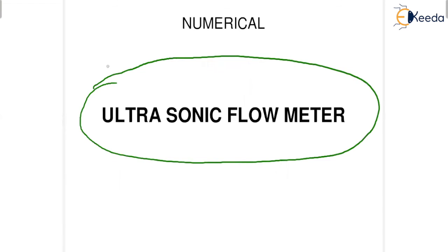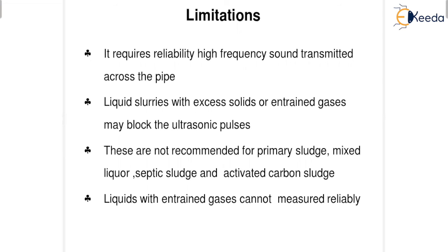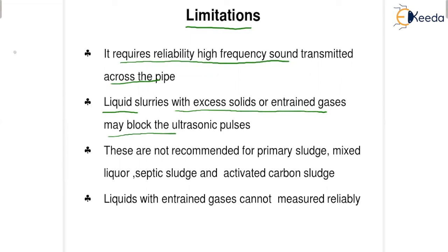Before that, I'm going to conclude with the limitations. It needs reliable high frequency sound transmitted across the pipe; it gives only stable frequency sound across the pipe. Liquid slurries with excess solids or entrained gases may block the ultrasonic signal. So the limitation is that the liquid passing inside the pipe should not be contaminated with slurries or solid particles suspended in the liquid.